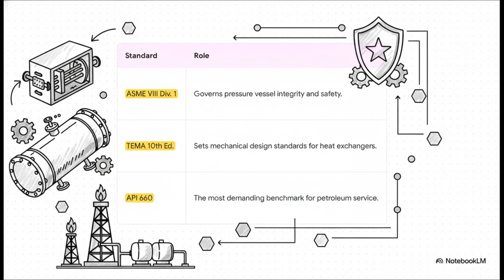Let's look closer at that compliance challenge. The cooler had to be a pressure vessel, so that's ASME code. It also had to meet the mechanical standards for heat exchangers under TEMA. Layered on top of that, it had to meet API 660, the gold standard for this equipment in petroleum service, which adds even stricter requirements for things like nozzle loads and maintainability.